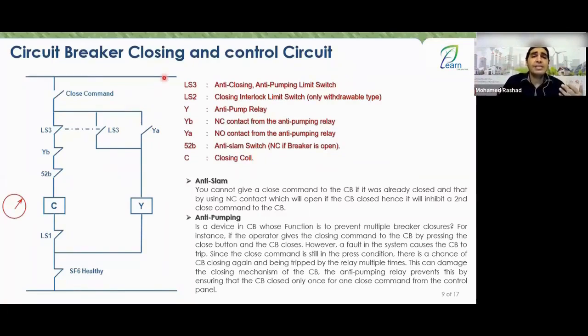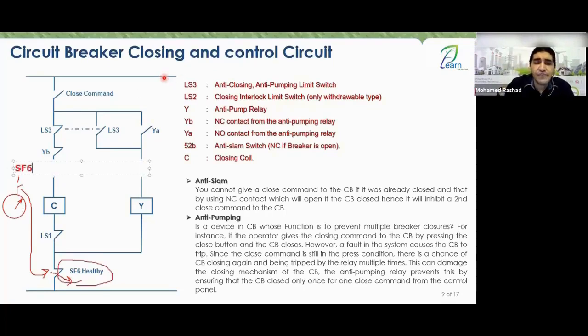That's why it starts to make contact here. This gauge, according to the gas pressure, has a set of limit switches. The limit switch is what I placed here, so that if the gas pressure is low, it opens the circuit here, preventing the circuit breaker from closing, because forming the arc would destroy the circuit breaker. At the same time, if you close the breaker and the gas pressure is low, a fault might occur, and the breaker will try to open. This also happens during a fault, meaning a current in kiloamperes. So imagine you're interrupting the spark of a kiloampere current. What would happen then? So where do I get this contact from? I get it from the SF6 gauge.